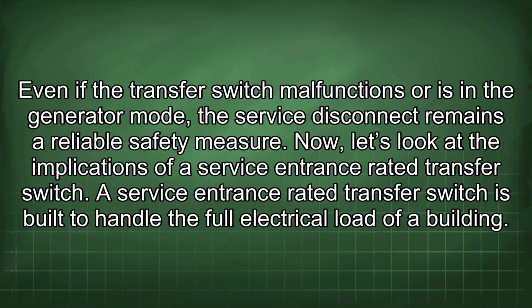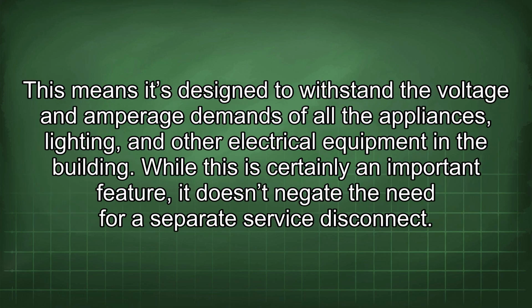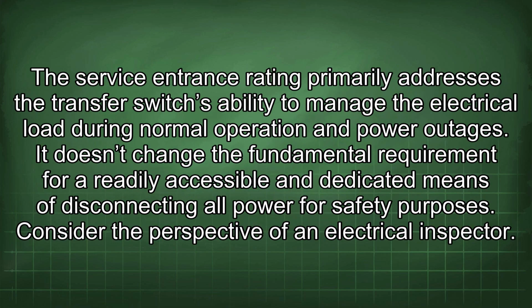A service entrance rated transfer switch is built to handle the full electrical load of a building. This means it's designed to withstand the voltage and amperage demands of all the appliances, lighting, and other electrical equipment in the building. While this is certainly an important feature, it doesn't negate the need for a separate service disconnect. The service entrance rating primarily addresses the transfer switch's ability to manage the electrical load during normal operation and power outages. It doesn't change the fundamental requirement for a readily accessible and dedicated means of disconnecting all power for safety purposes.